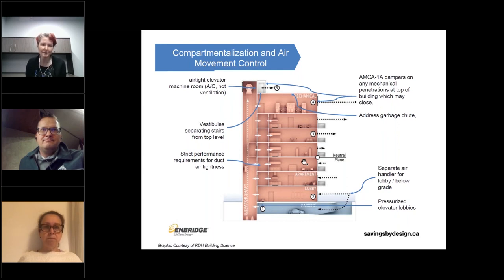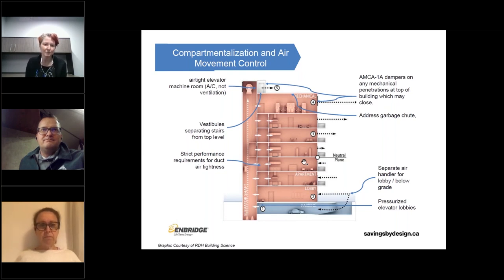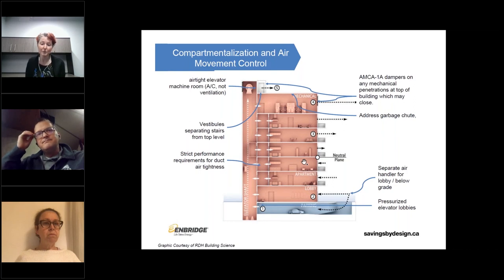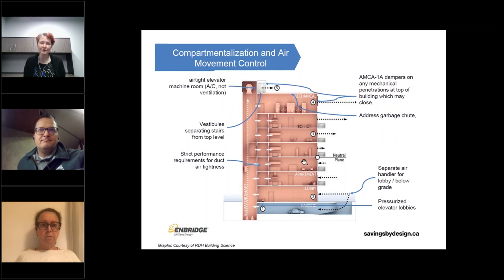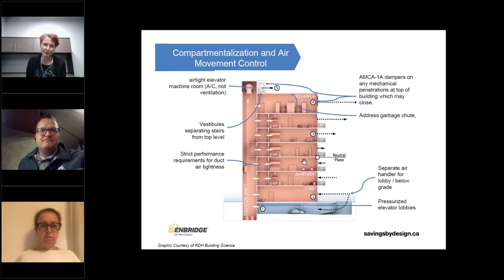Some specific recommendations moving top to bottom: the elevator is our biggest vulnerability. The code was updated to avoid penetrations in the shaft for energy recovery reasons, but we still have air movement from the shaft into the elevator machine room. It's important to think of the elevator machine room as a bathtub system — as airtight as possible and conditioned entirely with split systems rather than using a grill to allow free air conditioning through the outside wall. Anywhere you have penetrations at the top of the building, you'll want certified airtight dampers, AMCA-1A. You can also address garbage chute air leakage — there are code interpretations allowing a damper and fan rather than uncontrolled air, plus high-quality garbage chute door seals to reduce air movement.